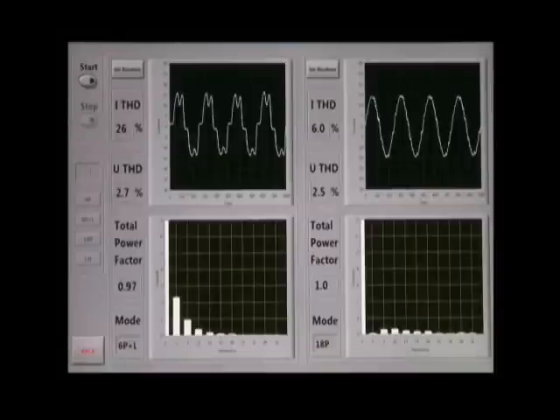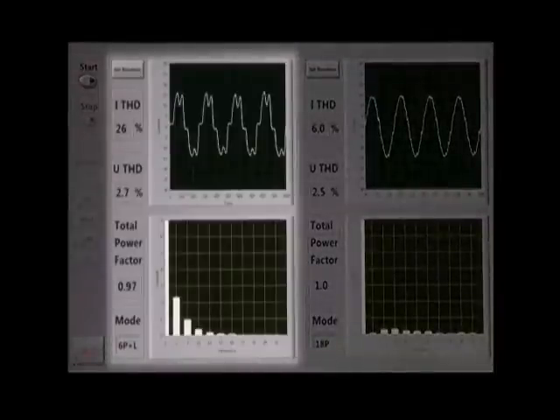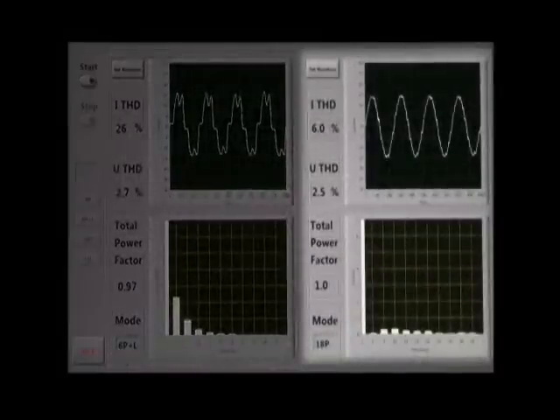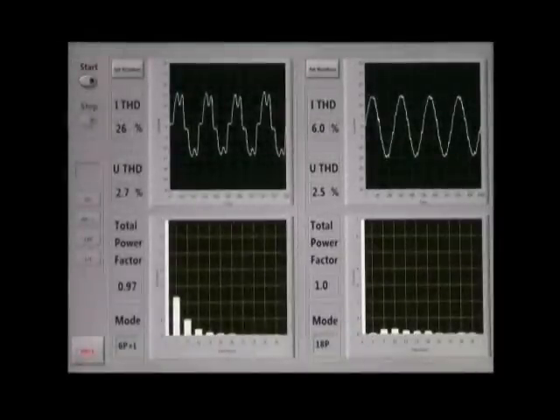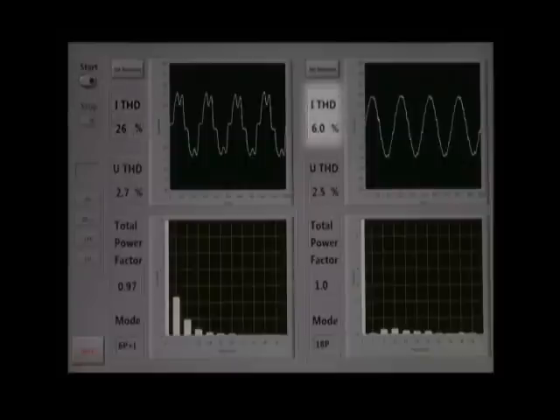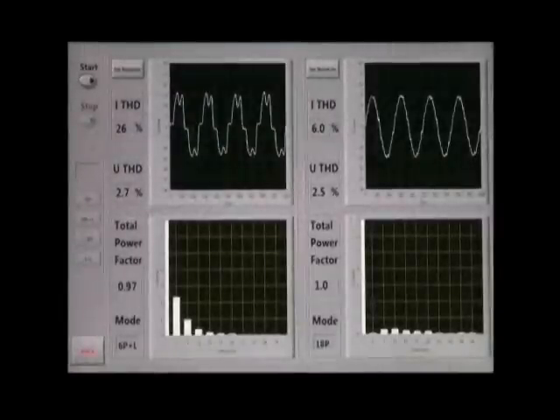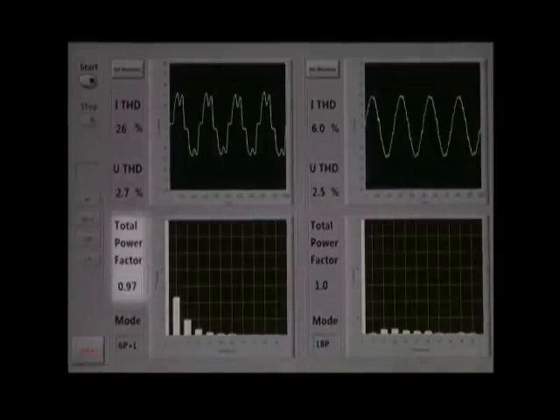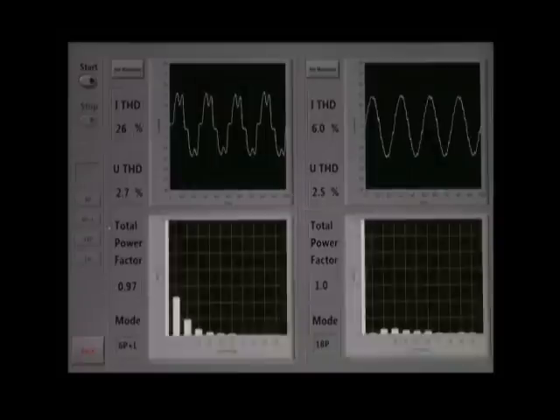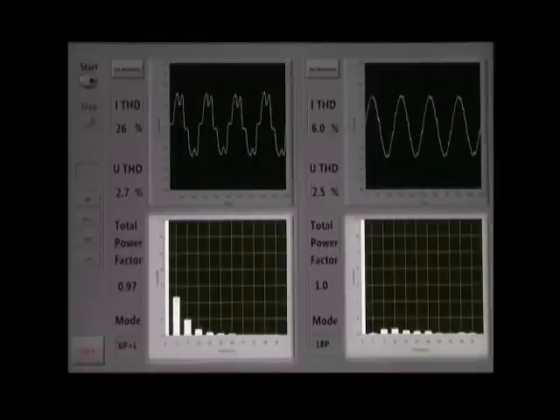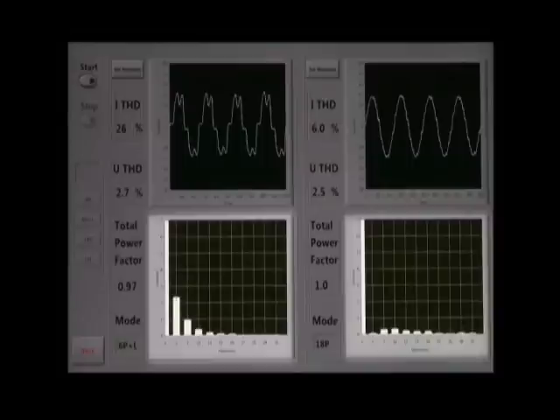Taking a few more captures of the operation in 6-pulse with inductor and operation off of the 18-pulse, we again can see the dramatic difference on all levels of harmonic performance. Current distortion has dropped from 26% down to 6%. Our voltage distortion has dropped from 2.7 down a little bit to 2.5. We've had a significant improvement in power factor. Total power factor has increased from 0.97 to 1, near unity power factor in this particular case. And if we examine in the lower graph the individual harmonic levels, we see that the 5th, 7th, and 11th harmonic levels have almost come off the screen.